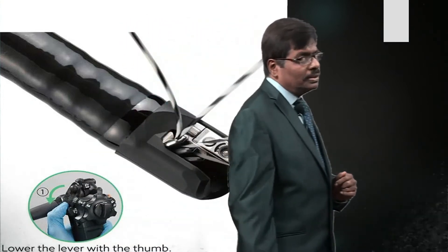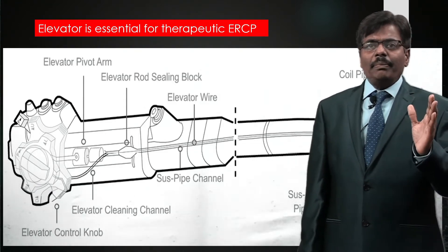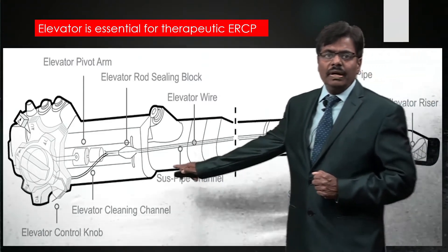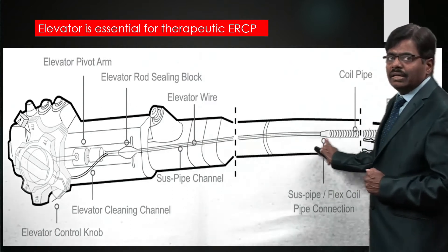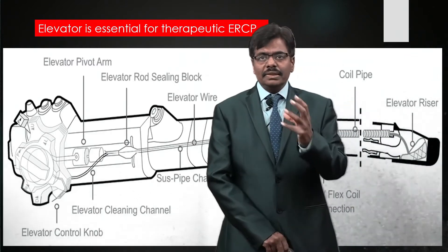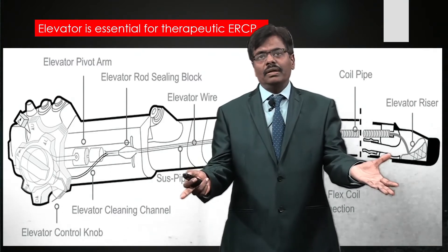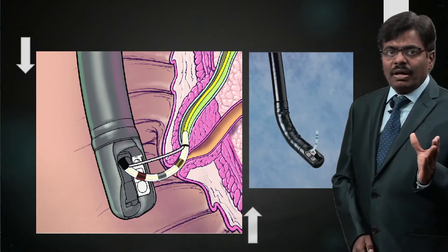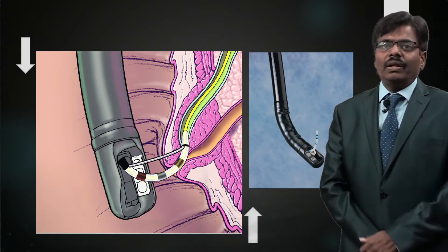The elevator mechanism is very delicate and expensive. You can see where it is attached, how the wire runs all the way through, and how it helps. If something goes wrong, they have to dismantle the entire duodenoscope to rectify the problem. Proper elevation and angulation will bring you to selective cannulation of either the PD or the CBD.